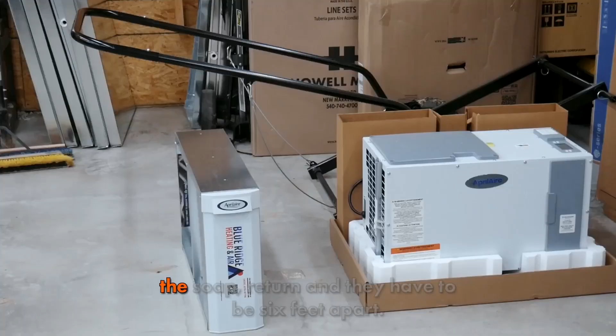The dehumidifiers, we hook them up to the return, and they have to be 6 feet apart so you're not recirculating the air within the dehumidifier and the ductwork. We like to tie them into the system, so when the dehumidifier calls for dehumidification, the blower comes on and recirculates it through the house, giving you dehumidified air throughout the whole home.